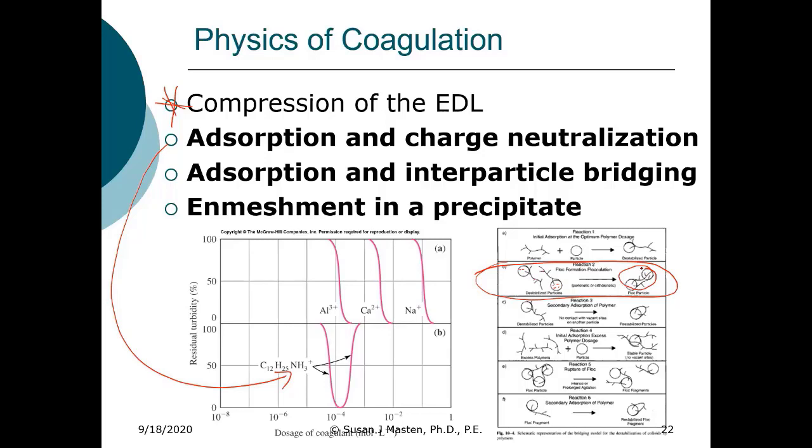Now, the challenge with this is that these doses of these organic polymers are very, very sensitive, or coagulation is very, very sensitive to the dosage. If you're not careful, you can see here we've got this particle, and the long chain bends, interacts with the particle, and you're not getting any interaction with another particle, and you simply just restabilize the particle.